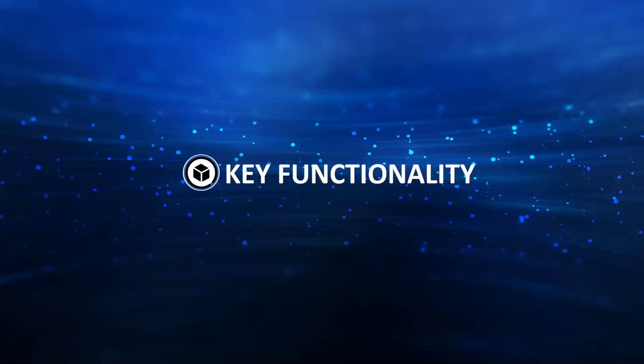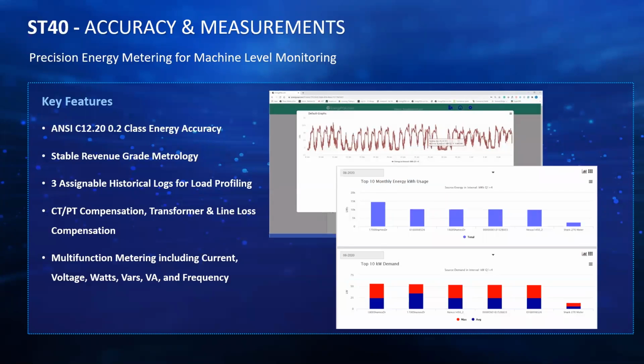Some key functionalities of the ST40 include revenue accuracy, like I just mentioned. We meet the ANSI C12.20 revenue accuracy standards. The ST40 is a stable revenue grade meter. This means that our 0.2% revenue accuracy capabilities include the entire range of voltages and currents that can be in the meter. Our meter is 0.2% accurate for current from the low range, where we're looking at 0.5 amps, all the way up to the 5 amp input of the meter. We don't require a full load situation to meet the 0.2% class revenue accuracy.